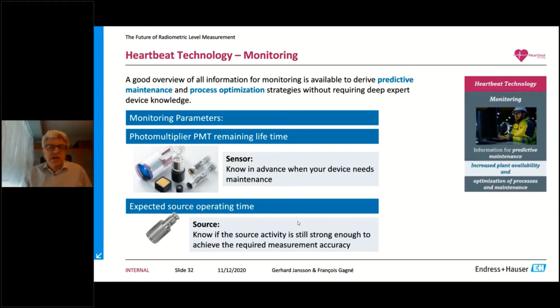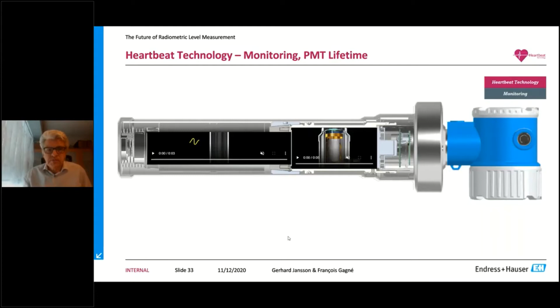So this is probably also an animation that doesn't really work out. Anyhow, this part here is the active part where we have some kind of material, either PVT, which is polyvinyl toluene, or sodium iodide. It's a crystal which will convert radiation to light photons. The light photons will then go into the photomultiplier, which will count them. They will be amplified and counted. And at the end up here would be a converter between the number of counts and a conversion to the analog output.